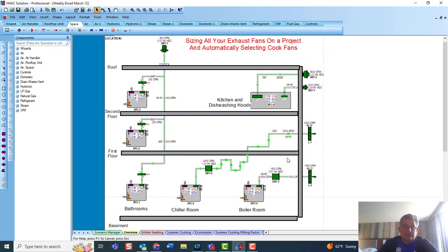Early on in a job, you can estimate your static pressure. After you've maybe done a 3D Revit model, then you can look at your model, and then come into the space and maybe show that you had a bunch of 90s, if in fact you did. A lot of times when the contractor builds projects, they'll go up and over structure, around ductwork, around piping, and a lot of times the static pressure on the exhaust systems ends up being a little bit greater. So it's always nice to leave a little bit extra static for those conditions.